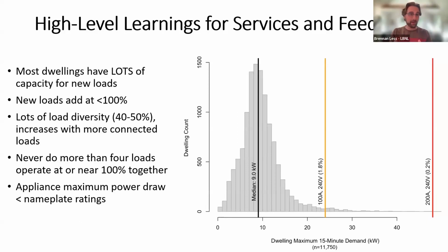Most homes just have a lot of spare capacity. We find that when we add new loads to homes, they don't add at their nameplate rating, so we can add them at substantially less than that. There's lots of load diversity, meaning all the loads are not on at the same time. We don't need an electrical code that says everything is on at the same time, add it together. We can account for that diversity. We find that effectively never does it occur that more than four loads are at 100% at the same time. So we've got opportunities to account for diversity and for treating loads at less than 100%.